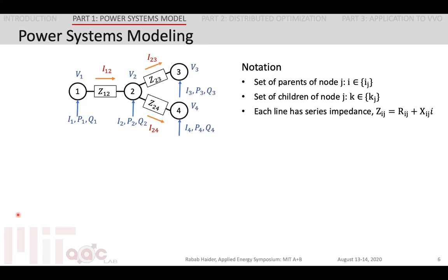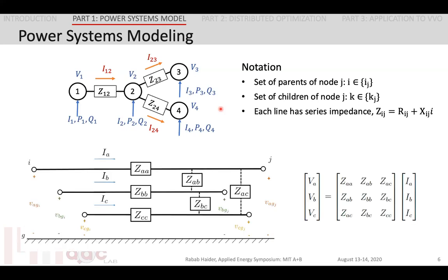We can begin by modeling the distribution grid. We take a current injection approach whereby the power injected P_j and Q_j at every node J is modeled by the current at that node, I_j. The rest of the model is characterized by the nodal voltage V_j, and then the current in the branch between nodes I and J, I_ij. We consider both radial and mesh topologies, and so a node may have a set of parent nodes, which for node three is node two, or a set of child nodes, which for node two is nodes three and four in this diagram. Finally, we modeled the line characteristics using the three-phase impedance matrix, which consists of the resistance and the reactance components of the line.